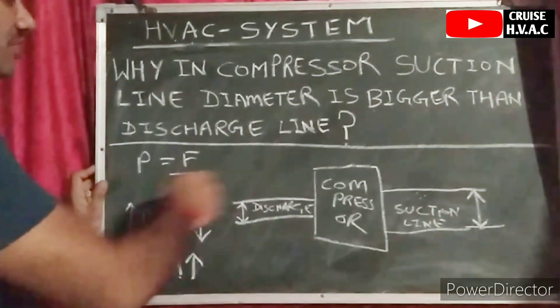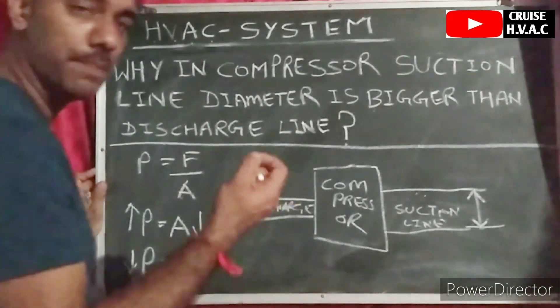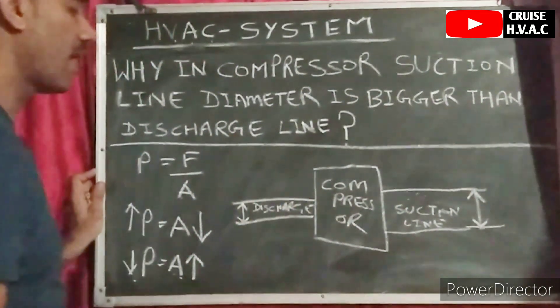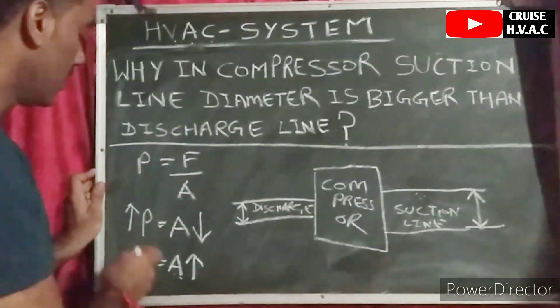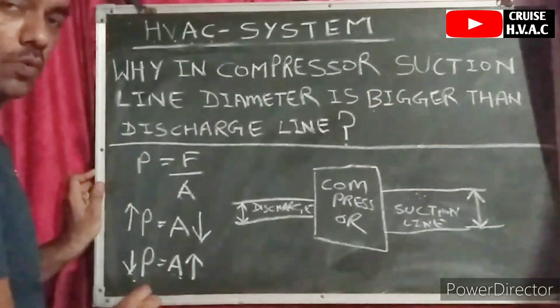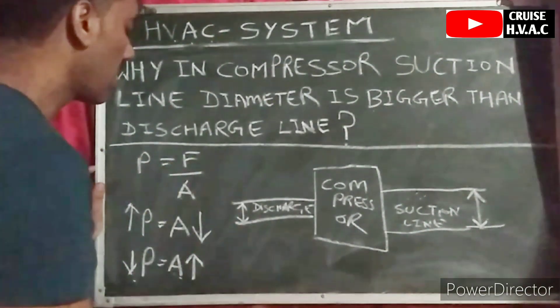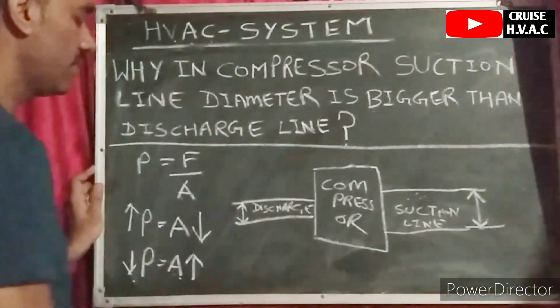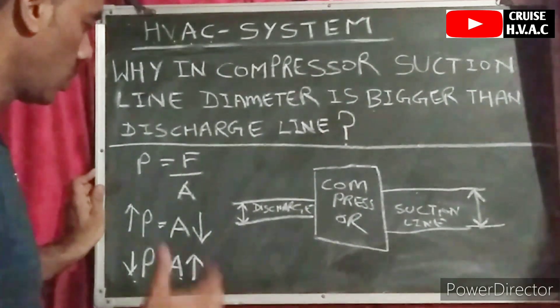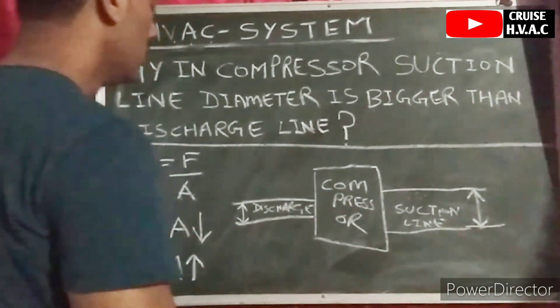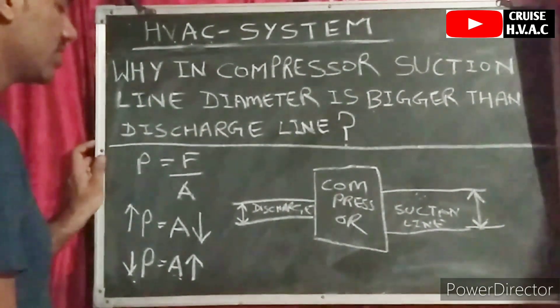On the discharge line, the refrigerant is in high pressure, high temperature vapor form. When the pressure is high, the area is low — that's why the diameter of the discharge line is lower compared to the suction line. The density of the refrigerant is also high in the discharge line.